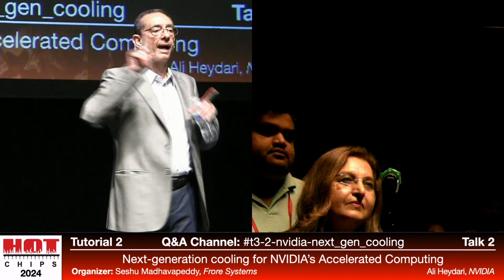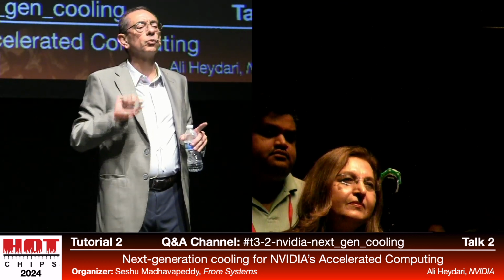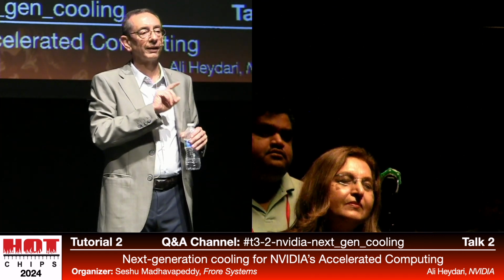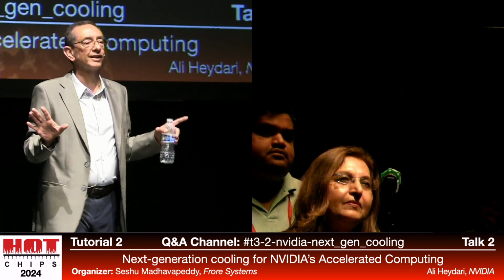Very good question, yes absolutely. So fidelity of CFD is very well known. When we build data centers, we basically build the data center with flow network modeling based on the fact that this entity I built is going to go through commissioning. Commissioning is a step where I bring load banks, liquid and air load banks, and test it out, testing the capability of a data center. So when I build the CFD, I test it with actual equipment with load banks and predict. Normally I'm within 1 to 1.5 degrees C of that. So we're not changing anything from existing practice.